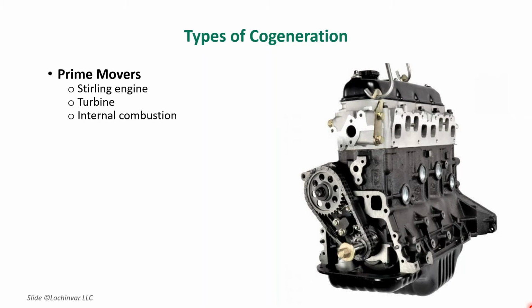It takes a little time overnight to let the engine cool down, so your main downtime is roughly 10 to 12 hours every 6 months if you're running this 24/7. In typical installed applications, we're experiencing basically one maintenance cycle a year, based on 4,000 to 6,000 hour runtime, running 16 to 18 hours a day minimum on a project. So again, we don't want to tear this engine apart.